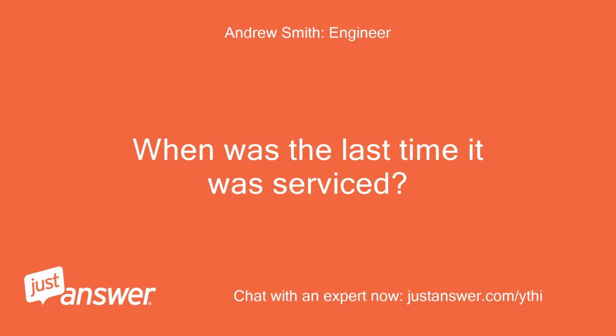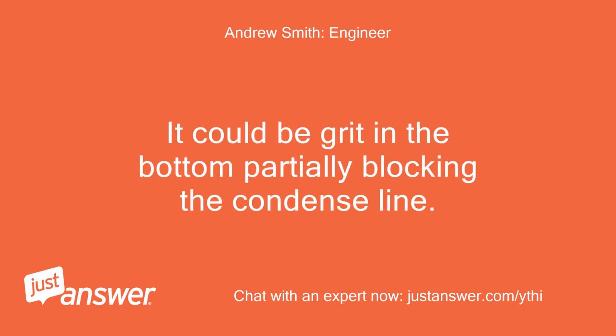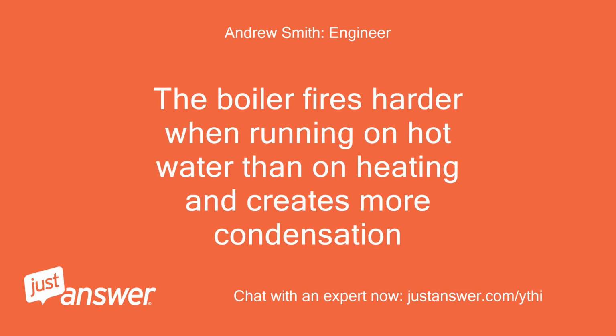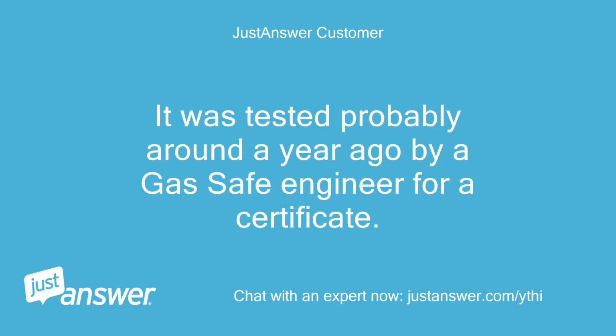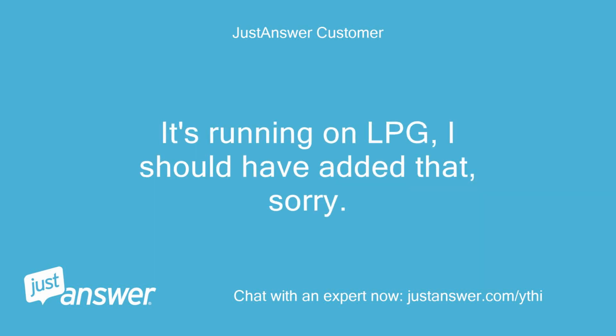When was the last time it was serviced? It could be grit in the bottom partially blocking the condense line. The boiler fires harder when running on hot water than on heating and creates more condensation. It was tested probably around a year ago by a gas-safe engineer for a certificate. It's running on LPG, I should have added that, sorry.